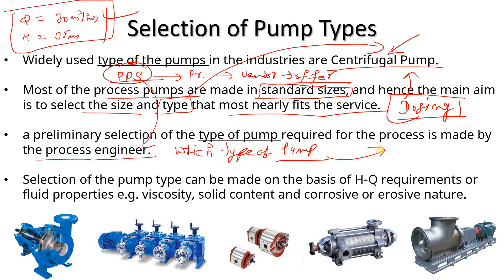There are selection criteria to keep in mind: head versus Q (head versus capacity) requirements, and the fluid properties of the fluid being handled — for example, whether it is water, slurry, or a chemical. What is the viscosity of the fluid? Is there solid content? Is the fluid corrosive? Does the fluid have an erosive nature? These points are very important when selecting a pump.